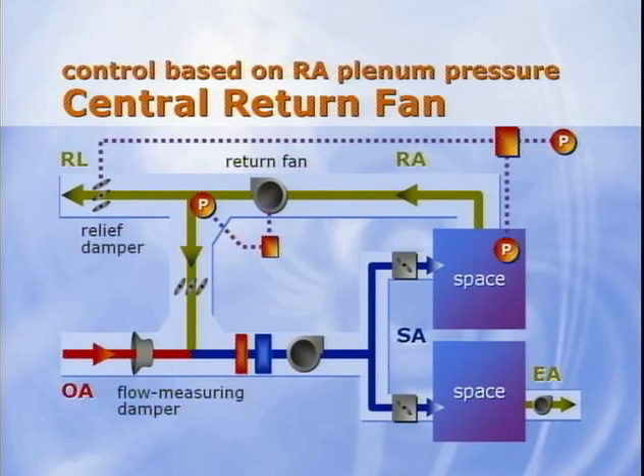In order to complete the ventilation loop, it has to run whenever the supply fan runs. Also, the return fan must be sized to support the maximum CFM of the return air at the worst case return static. Interestingly, this is probably not on an economizer day because supply airflow is lower. Rather, sizing needs to be done for a design day when supply airflow is at its maximum. Because the return fan is located in the return duct, one of the benefits is its ability to overcome high return duct static losses.